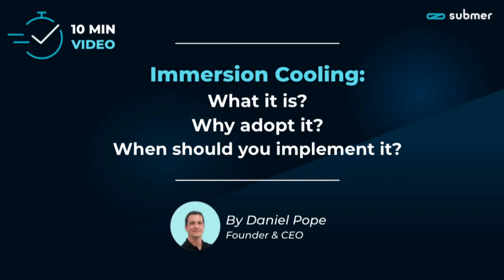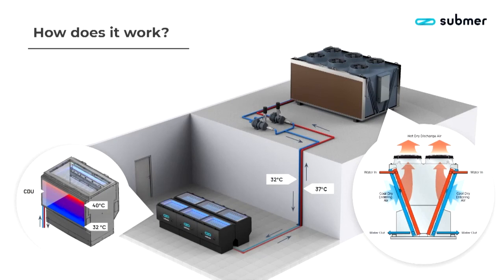How does it work? As we were mentioning, there's a water loop connected to the immersion tanks. The tanks transfer the heat. The CDU technology, cooling distribution unit technology, captures the heat from the IT equipment and transfers it to the water loop, and that water loop runs either outside, or we have a heat exchanger in between where we can activate energy reuse. But the whole idea is that it's a very simple installation, with a redundant pumping system for the water loop like any data center has today. And if the outdoor coolers or evaporative coolers, chillers, etc. are replaced with dry coolers, that's where we gain the biggest efficiency.